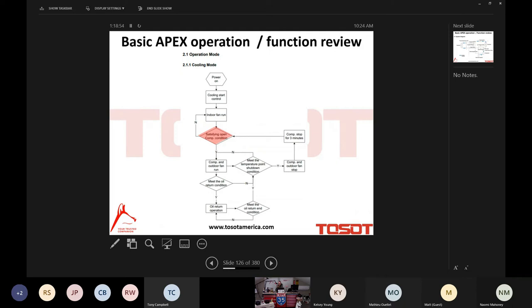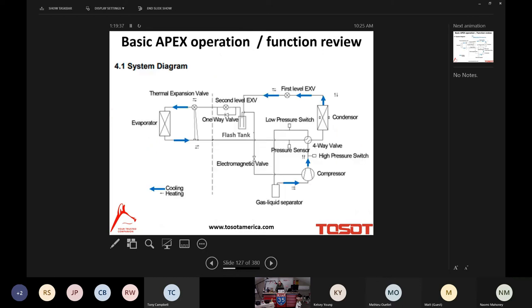I want to stop there just for a minute. So the compressor is always going to have this 3 minute on and 3 minute off cycle. I'll talk about why. The 6 minute off cycle is to prevent short cycling. The compressor will always be off for 3 minutes. And then on the next call for cooling, in this example, it's going to take 3 minutes for that compressor to start again, for a total of a 6 minute delay. This is good for the inverter compressor. So that's why you have that 3 minute off and then 3 minute delay again for it to start.